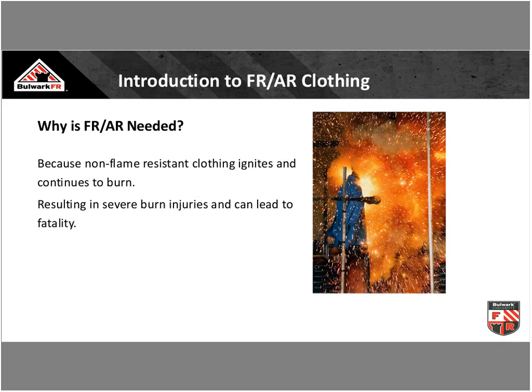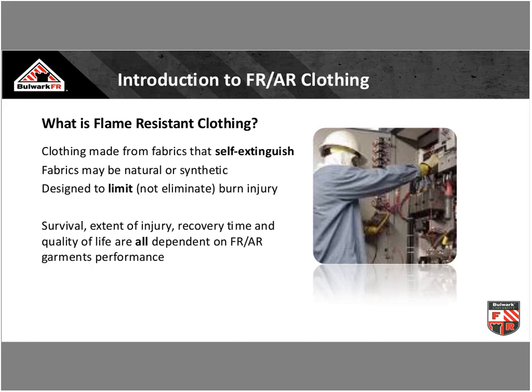Why do we need flame-resistant arc-rated clothing? Because non-flame-resistant clothing will ignite and continue to burn, resulting in severe burn injuries that can ultimately lead to fatalities. Remember, arc flashes, or our other hazard for flame-resistant clothing, flash fires, are in and of themselves so short in duration and intensity that they cannot by themselves lead to fatality. It's the clothing igniting and continuing to burn that ultimately causes catastrophic body burn and leads to that fatal outcome. So anything we can do to drive body burn down and mitigate injury where we can, we want to do, and that's where your flame-resistant arc-rated clothing comes in.